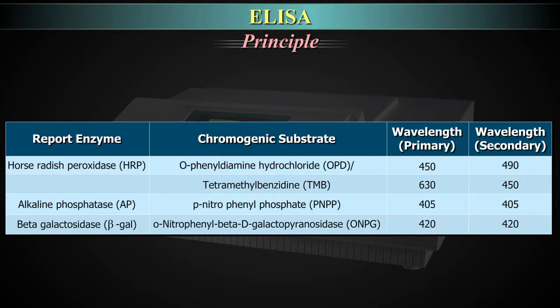For the same reporter enzyme HRP, when the chromogenic substrate is tetramethylbenzidine or TMB, the wavelengths are 630 nm for primary and 450 nm for secondary wavelength. When the reporter enzyme is alkaline phosphatase AP, the chromogenic substrate is PNPP, which is p-nitrophenyl phosphate. Here, the primary wavelength is 405 nm and the secondary wavelength is also 405 nm.